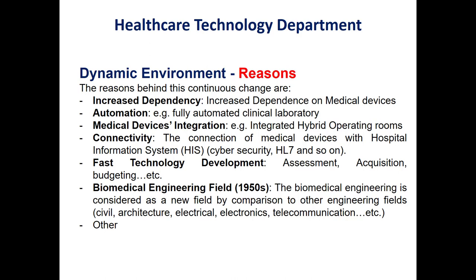Another reason behind this dynamic environment is connectivity — the need to connect all medical devices to the hospital information system. This requires knowledge of the right format, which is HL7 (Health Level 7), for connecting medical devices to the health system. Another concern is cyber security: adding medical devices to the health network increases the need for cyber security awareness. Additionally, the fast development of technology requires staff with skills in technology assessment, acquisition, and budgeting.